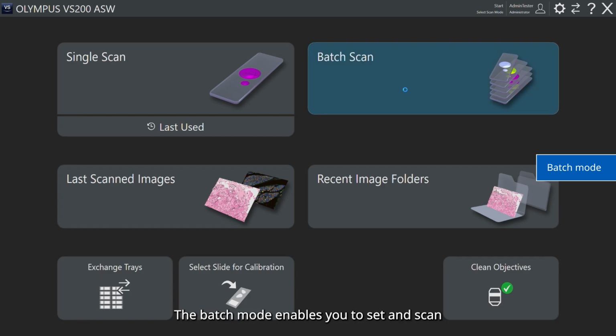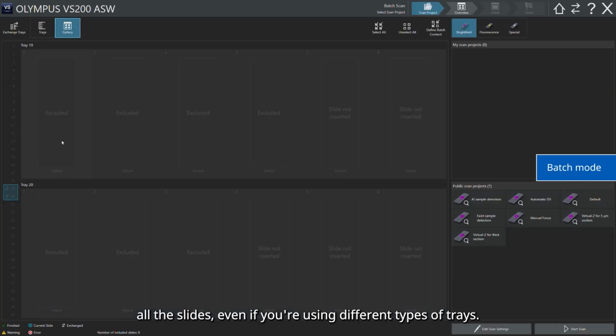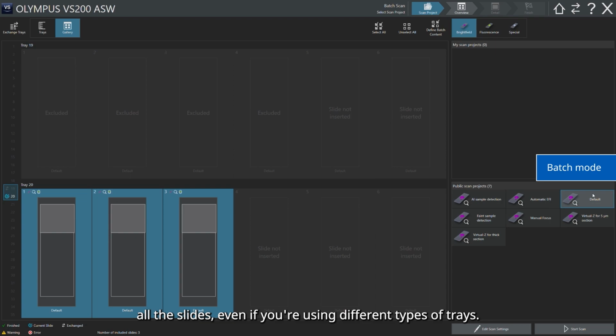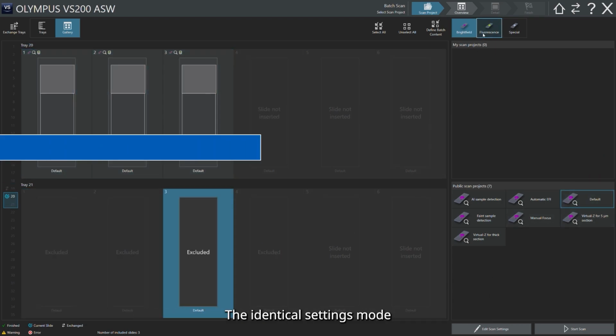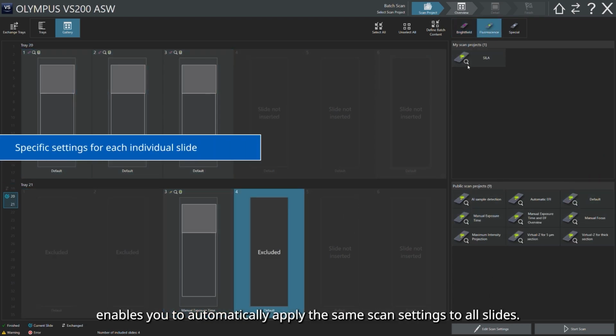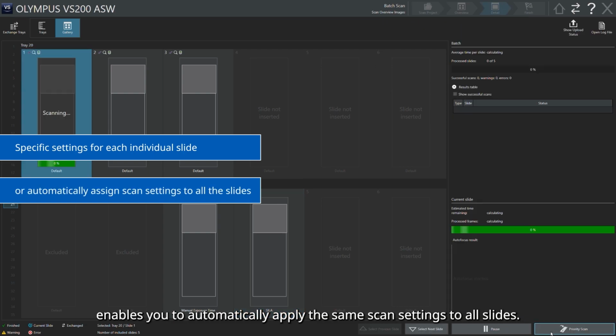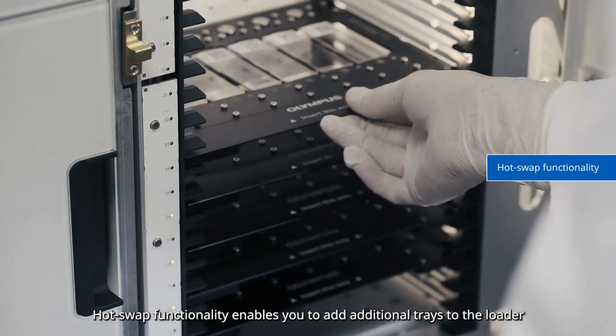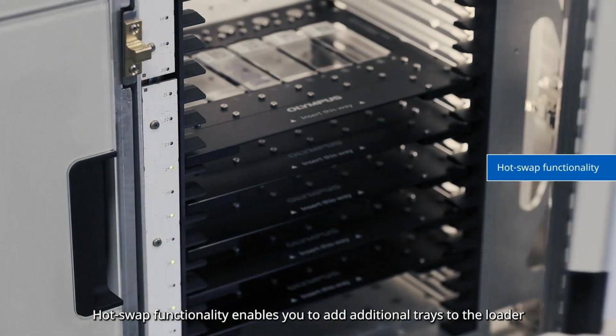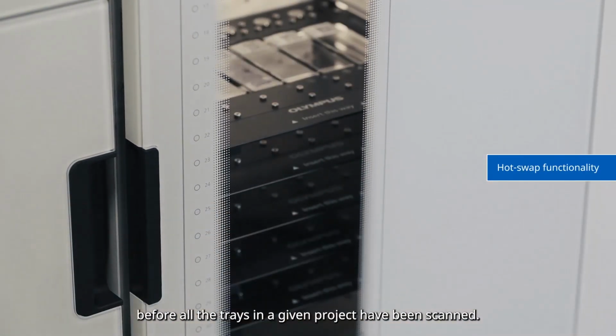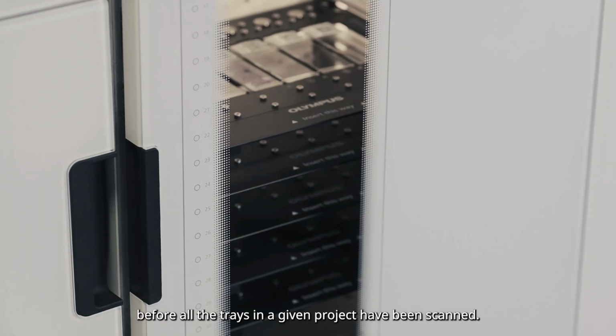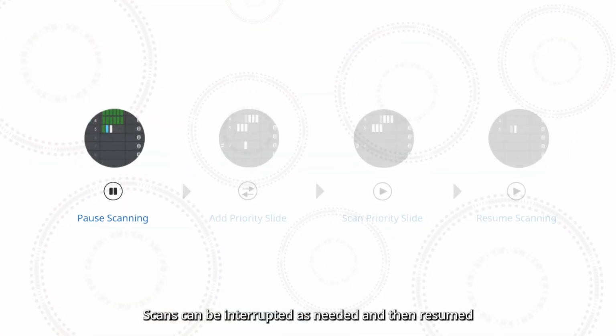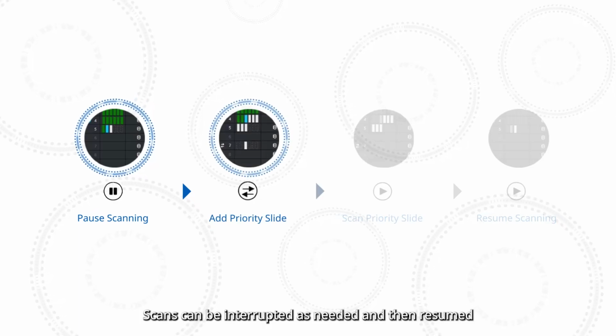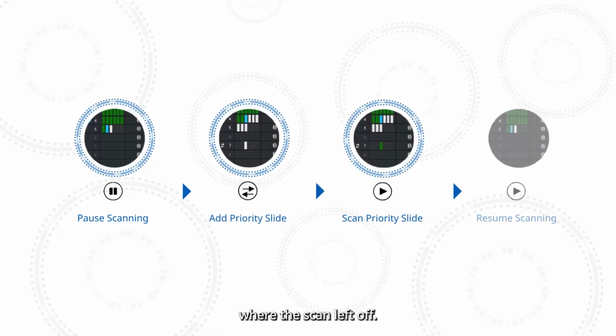The batch mode enables you to set and scan all the slides, even if you're using different types of trays. The identical settings mode enables you to automatically apply the same scan settings to all slides. Hot swap functionality enables you to add additional trays to the loader before all the trays in a given project have been scanned. Scans can be interrupted as needed and then resumed where the scan left off.